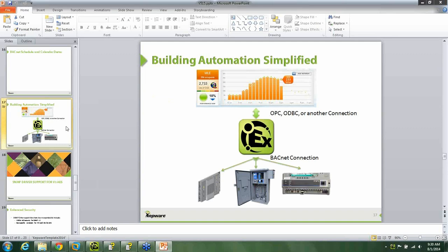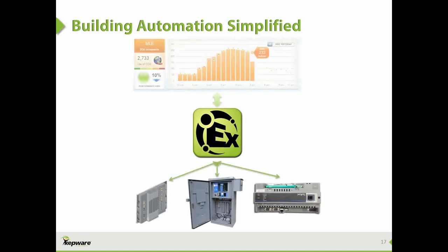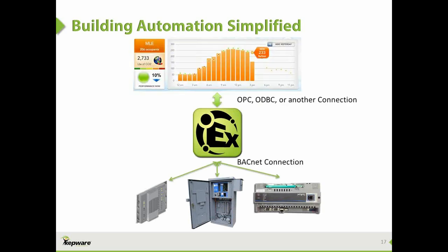Okay, so in summary, the new BACnet enhancements allow users to dynamically change these calendar and schedule objects. You saw in the beginning of the presentation, I did that through the KMC web interface. But if I wanted to control that information through an HMI or anything that has an OPC connection, or even, like we were talking about, log information to a database using Kepware's ODBC connection options like data logger, we can bridge that information from the BACnet controller to anything else. Basically translate it from BACnet to any other protocol or other connection. So that's where the power for that functionality comes into play.